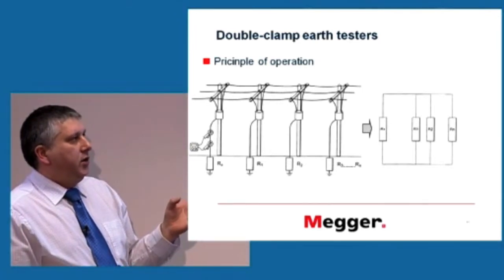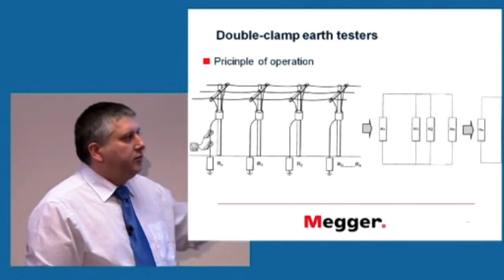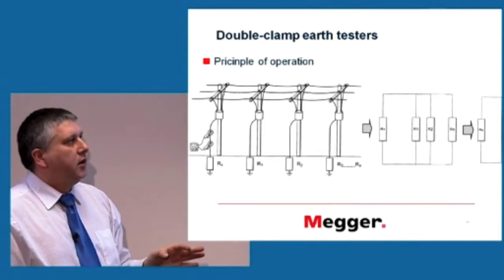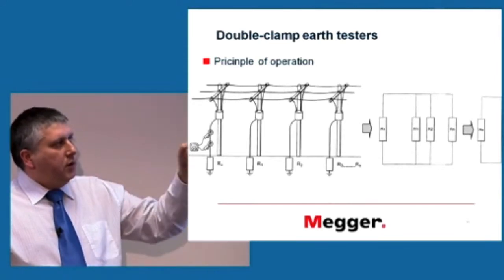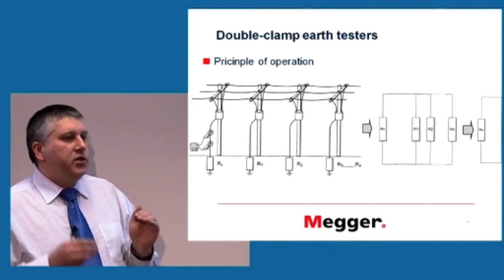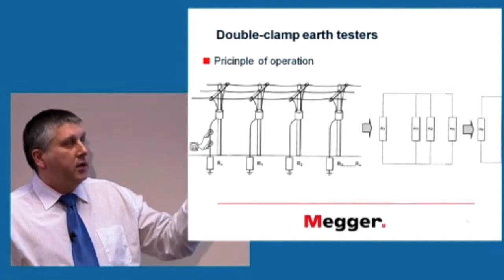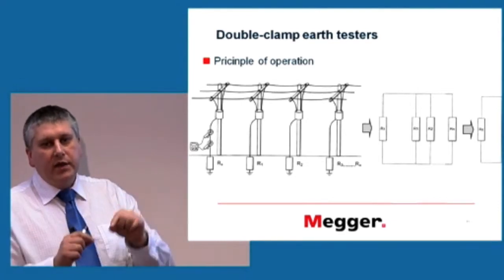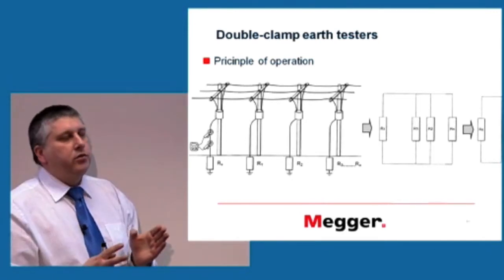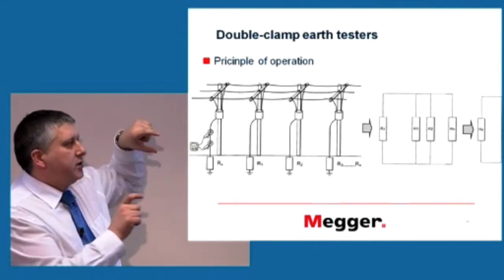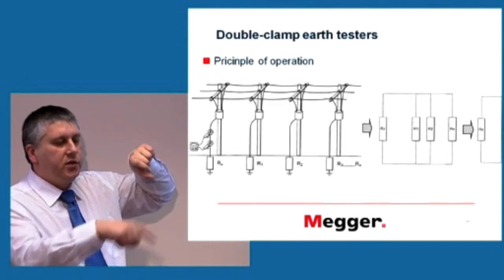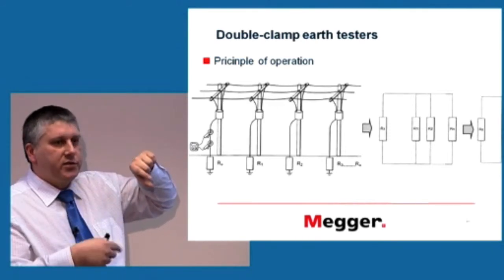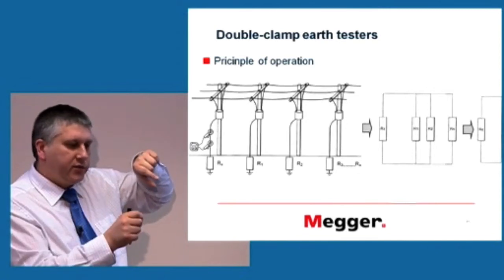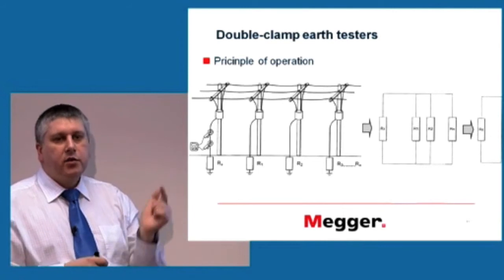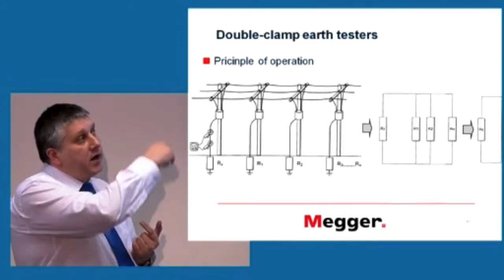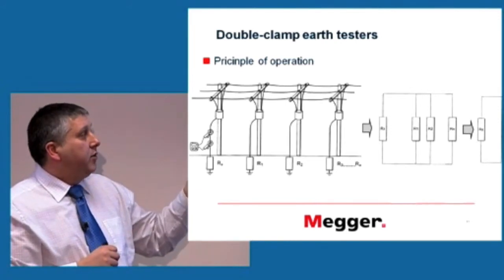And if we say that there are many of these electrodes, more than 10, say, the combined resistance of the many electrodes compared to the electrode under test is going to be much, much lower. Effectively, we have a short circuit everywhere else, but at the electrode we try to measure. So we can clamp our two devices around that electrode. One transformer will be inducing voltage in it. Because we have resistance, we have a loop, and a current will flow. We can then clamp another transformer to measure that current. Knowing voltage, knowing current, and knowing Ohm's law, we can calculate the combined resistance of that loop, which allows us to very quickly assess each of the electrodes.